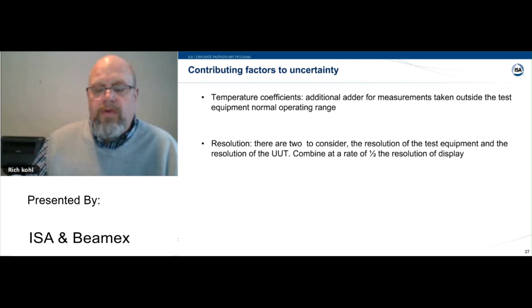If you're outside of your operating range, for example, I mentioned the top end was 28 degrees C for an operating range. You might be at 29. So how much does that affect your calibration? A typical TempCo that I used to work with was 0.05 degrees C per degree C outside of the operating range. And that was good all the way up to, say, 50 degrees C ambient temperature. Above that, you shouldn't use it at all. So that just gives you an idea. You can see where these TempCos can add up pretty fast, where you're at a couple of tenths of a degree when you're just a few degrees out of range.